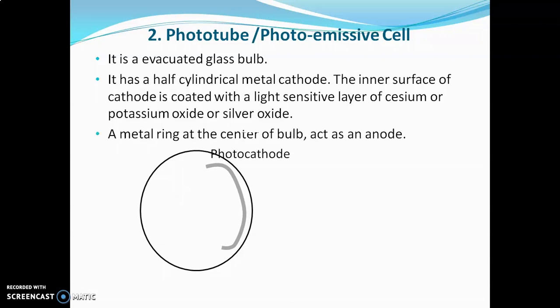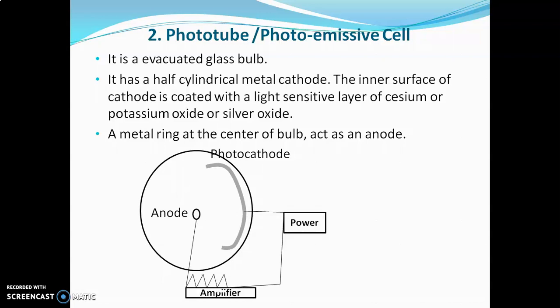The phototube consists of an evacuated glass bulb with a half-cylindrical metal cathode whose inner surface is coated with a light-sensitive layer of cesium, potassium, or silver oxide — called the photocathode. A metal ring at the center acts as the anode. The cathode and anode are connected through an external circuit with an amplifier. When light hits the photocathode, electrons are ejected and attracted towards the anode, generating current proportional to the incident light.